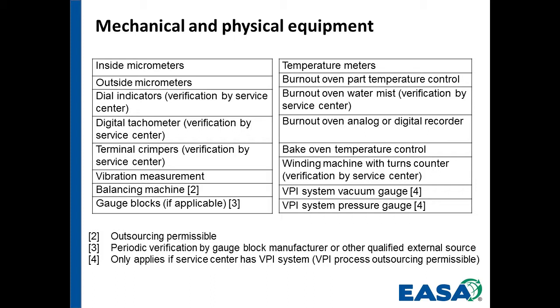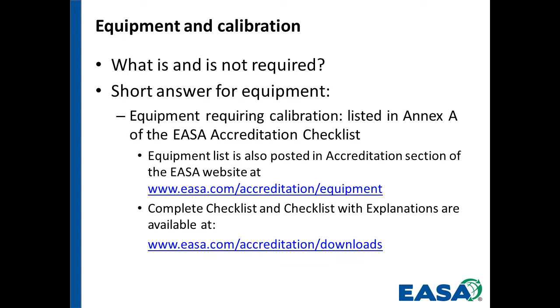Winding machine verification, turns counting. If you have VPI, then the gauges, the vacuum and the pressure gauges, need to be calibrated. And that's a key point, as simple as it is. One of the big things, not one of, but the biggest thing I have found and seen from audits is that calibration is the number one issue. And if someone has a VPI system, I'm not saying it's the number one issue with someone with a VPI system, but it's unusually high the number of times that someone with a VPI system has an audit and they find that their gauges aren't in calibration. In other words, the calibration date has passed. It's out of calibration by calibration date.